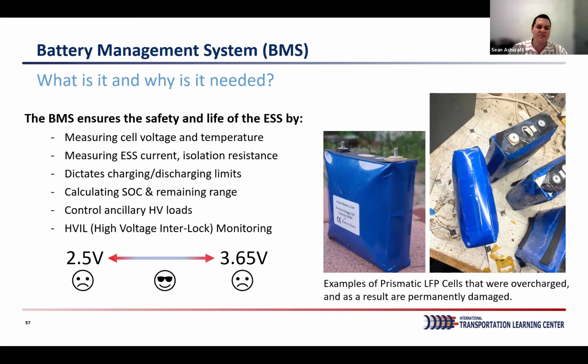Cell voltage and temperature are the 2 main data points that the BMS takes into account to dictate allowable charging and discharging limits of the energy storage system. The BMS also measures the energy storage system current, useful for calculations such as range estimation, SOC (state of charge), and battery health.